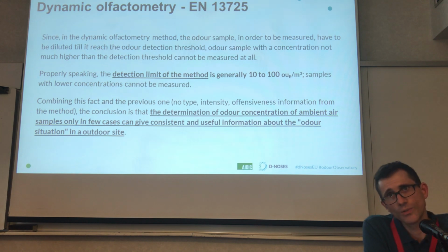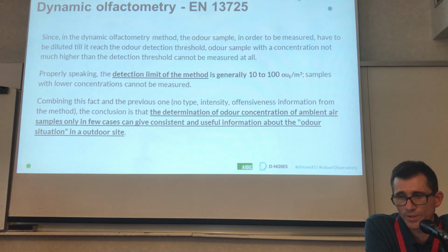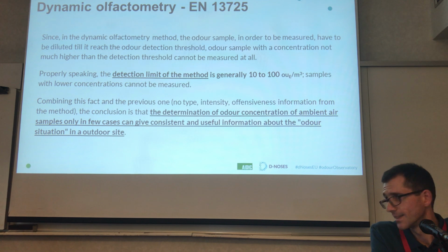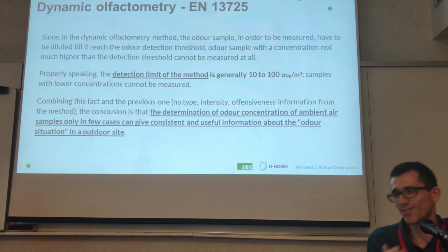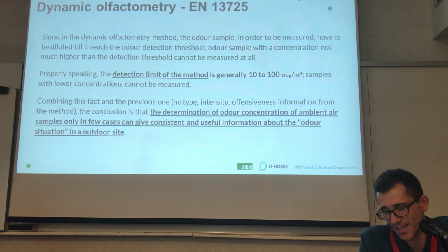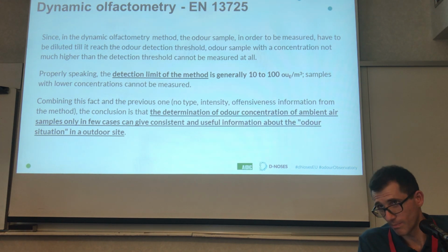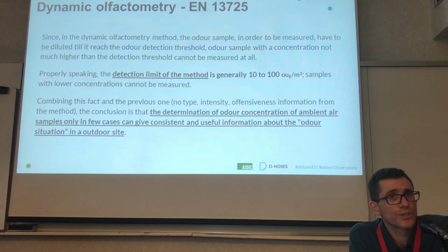This is a quite questionable way of working, because first of all, the detection limit of the method is generally from 10 to 100, or, very optimistically, from 20 to 50. Odor concentrations below 10 are not possible with the olfactometers on the market.